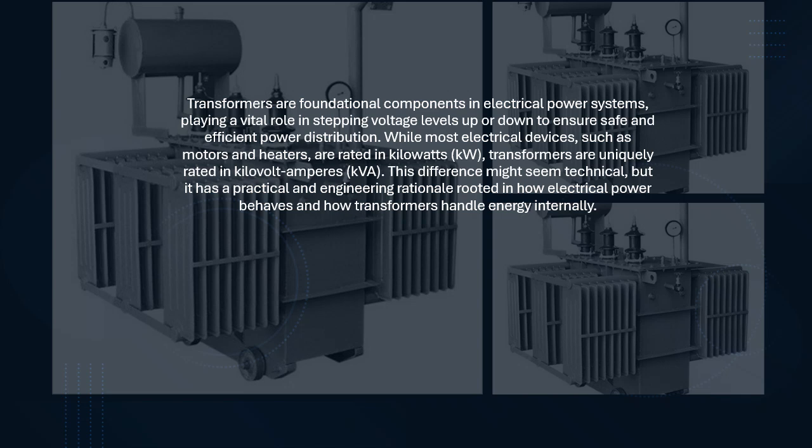While most electrical devices, such as motors and heaters, are rated in kilowatts, kW, transformers are uniquely rated in kilovolt-amperes, kVA. This difference might seem technical, but it has a practical and engineering rationale rooted in how electrical power behaves and how transformers handle energy internally.